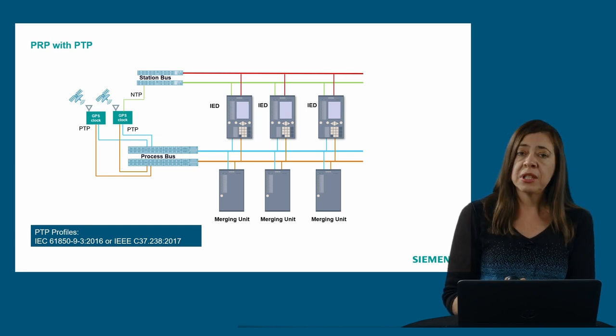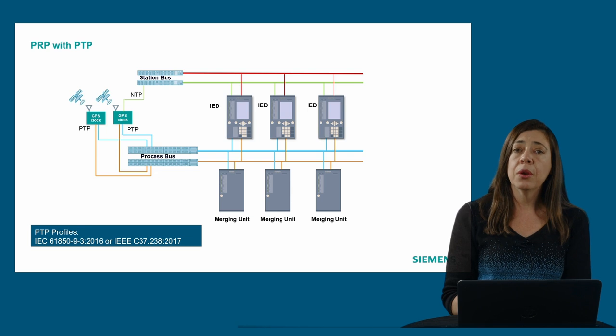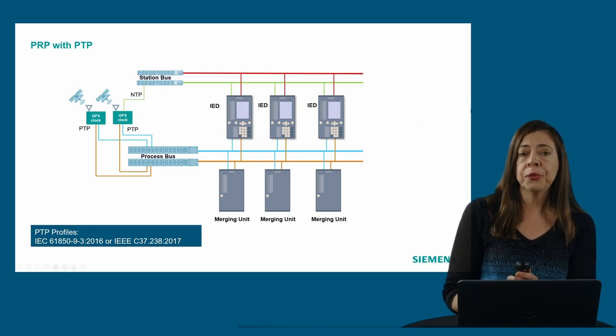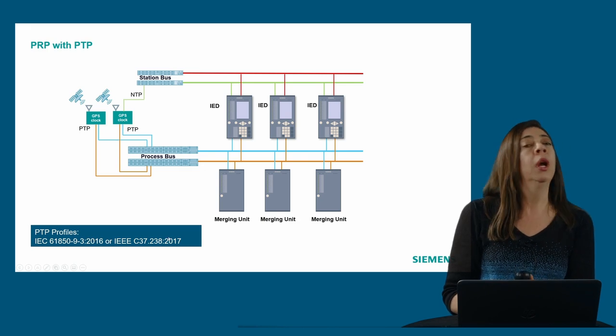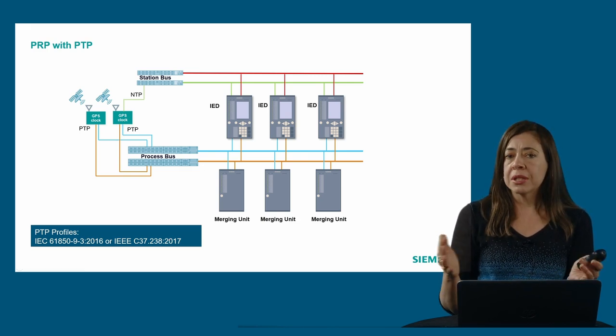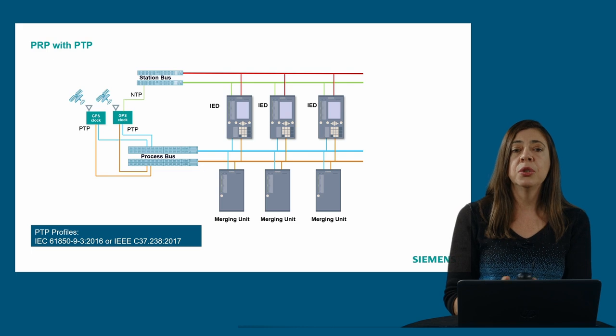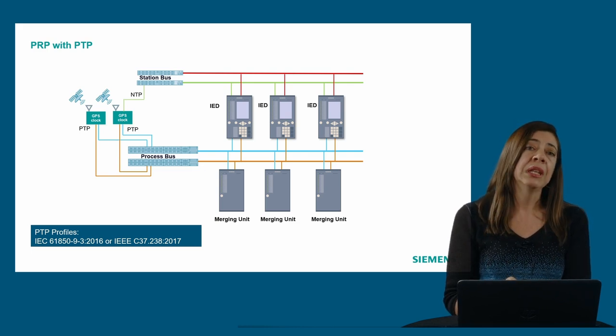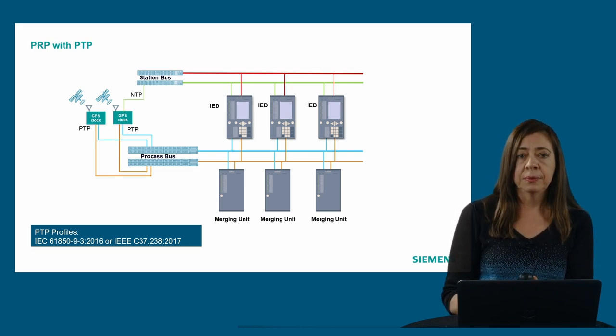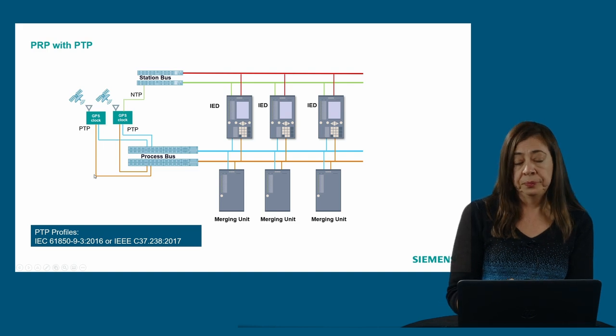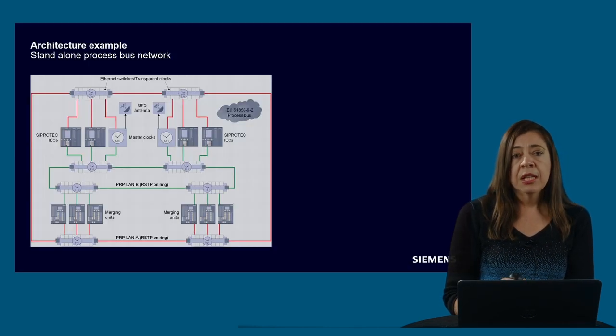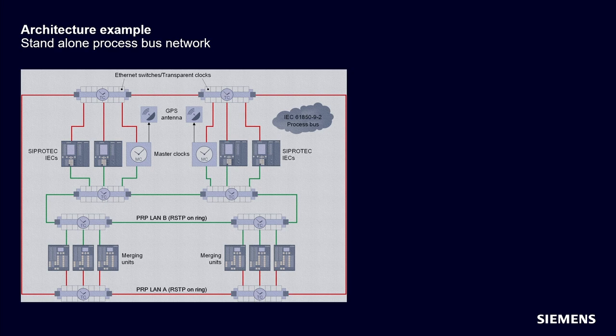For PTP, the SIPROTEC 5 devices are supporting two profiles: the power utility profile according to the IEC 61850-9-3 and also the power profile, the version from 2017. These two profiles can also be made available as interoperable. Just keep in mind that you need to give the right settings. So now let's see a little bit more complex network.